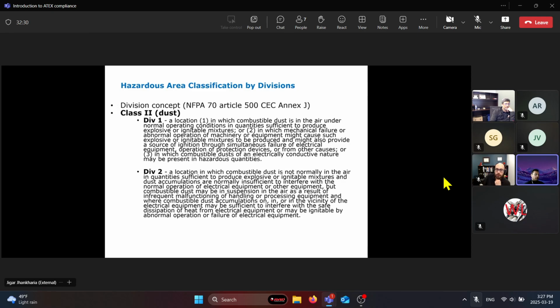So moving on to dust, again, Division 1, Division 2, same concept, except the environment is combustible dust, nothing different. The concentrations are the same as gases in a Division 1 environment or Division 2 environment, except there is only combustible dust and no gases present. So again, most of the time you would only find combustible dust in anyone processing logs or things like that, like timber or similar applications, normally not in an oil and gas application.